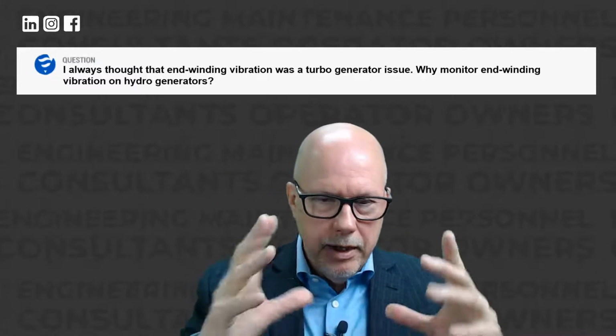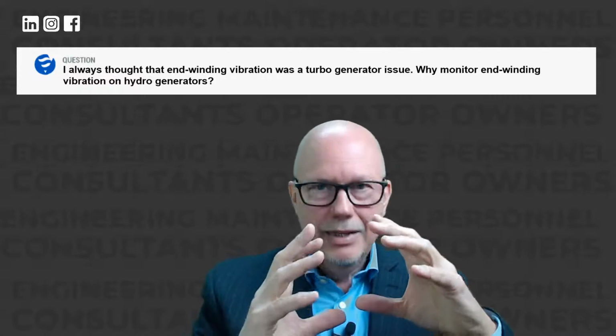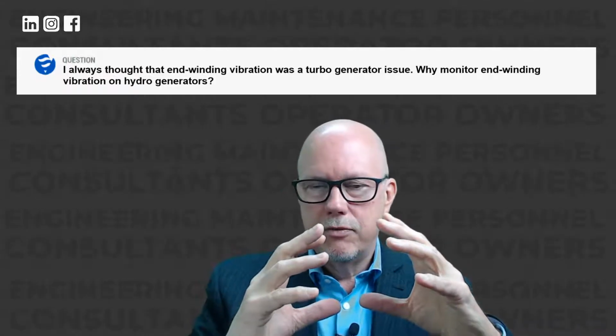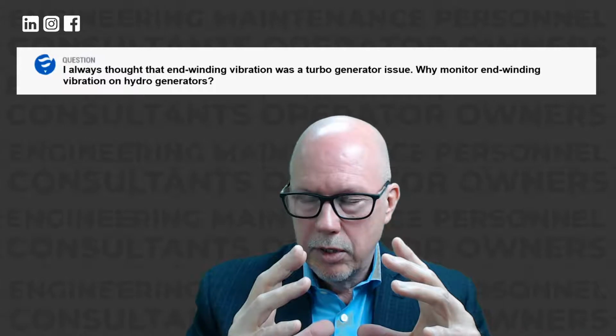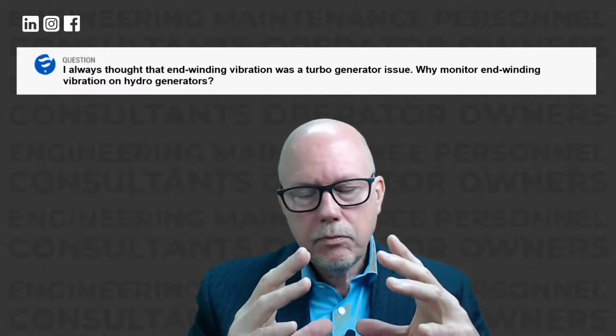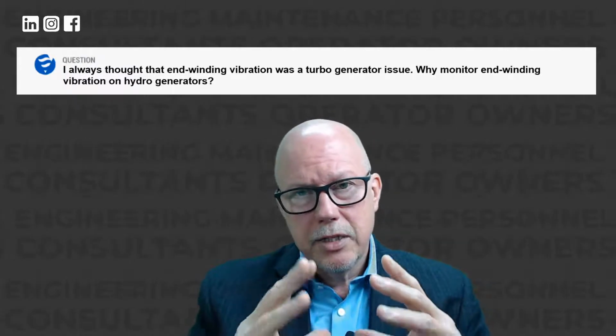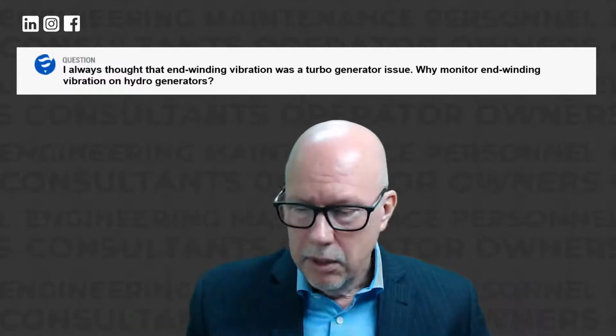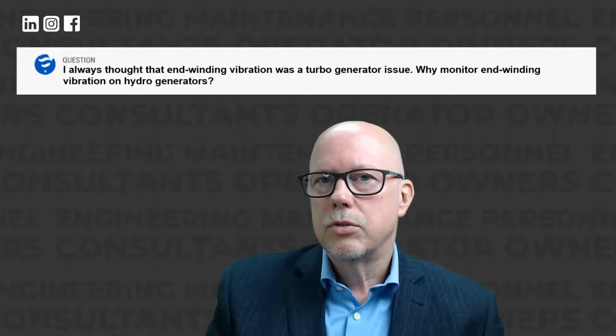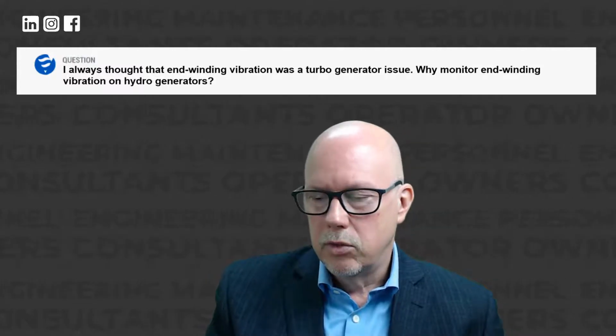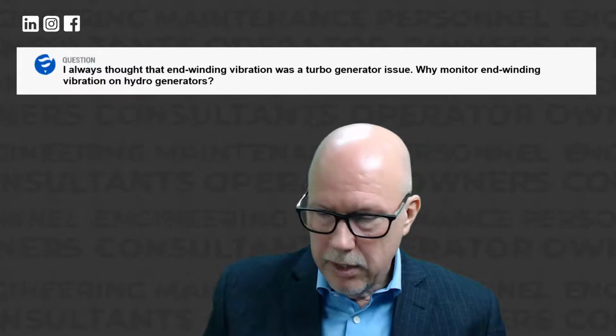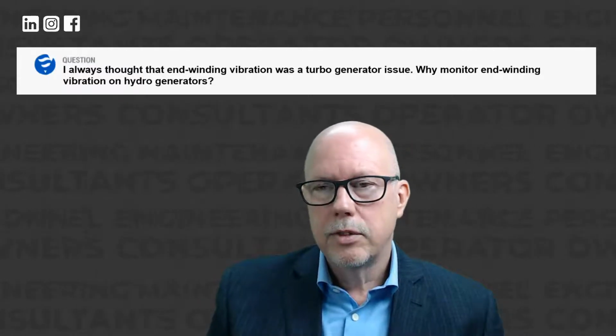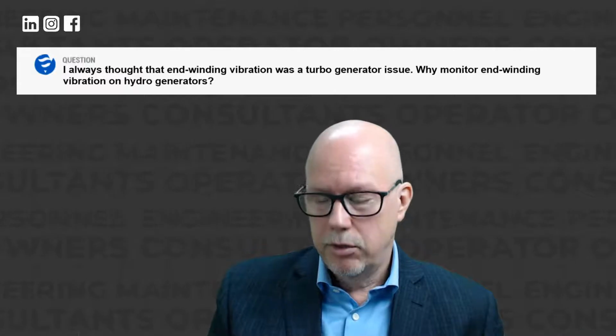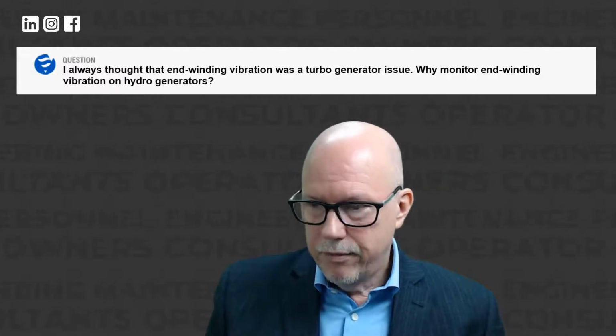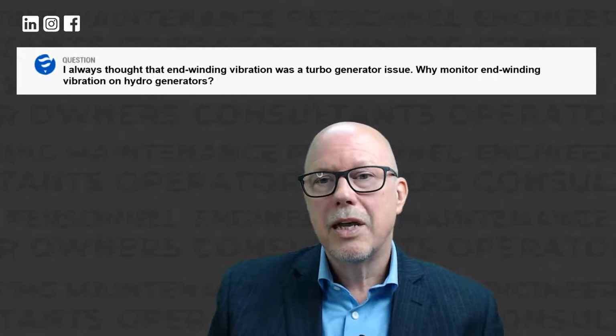So the consolidated basket is difficult to maintain. It's difficult to make it very stiff so the vibration doesn't occur, or is limited, but also very flexible to allow for the expansion and contraction based on the heat which is present. So they have many more issues on their end windings than on hydro. However, we've been installing on hydro generators and also on motors in the mining industry because we find there are issues on those as well.